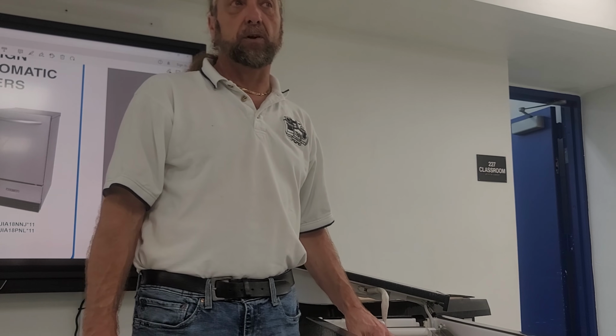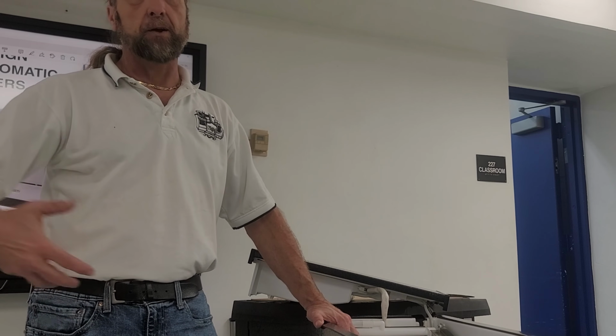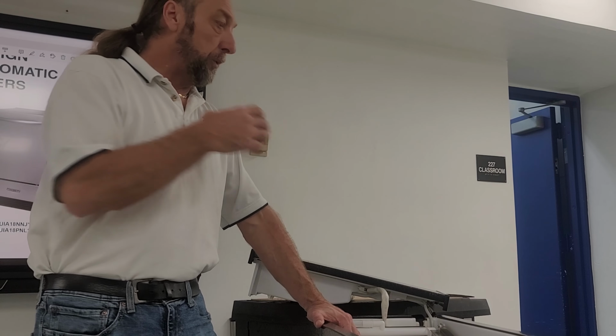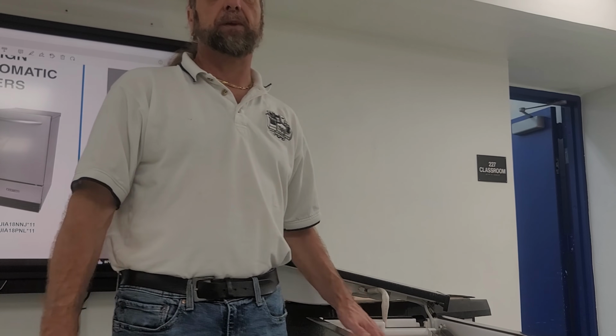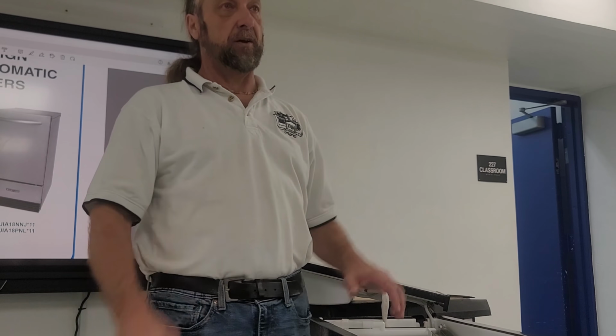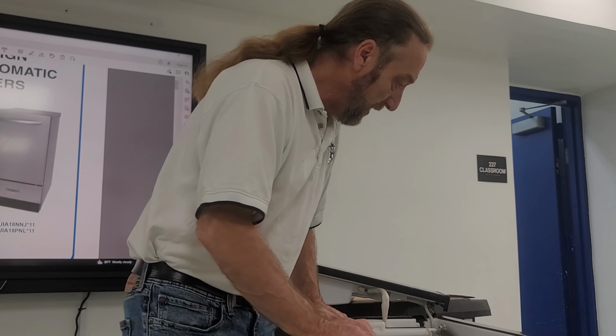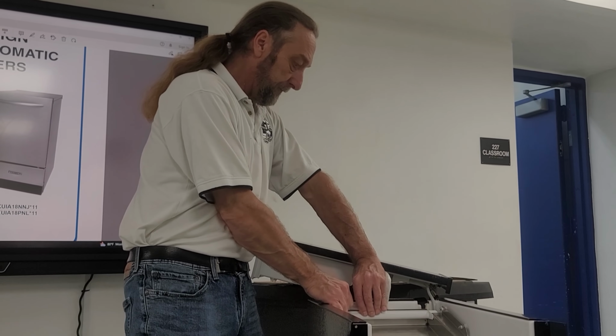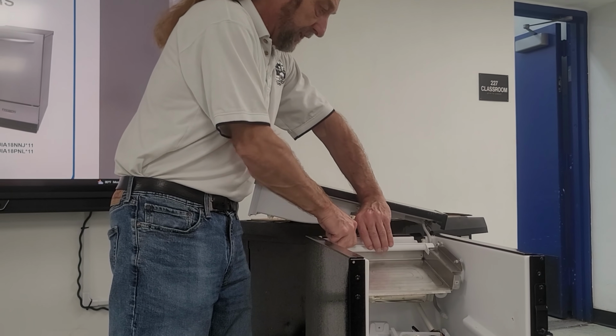So how we check for a leak is, when the compressor's not running, we get the refrigerant out, and we put nitrogen to 100 PSI when it's not running, and then we can soap test this and see if it bubbles with the 100 PSI. So I'm going to go ahead and disconnect this recirculation hose here.